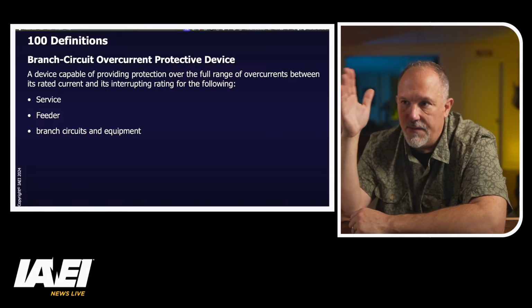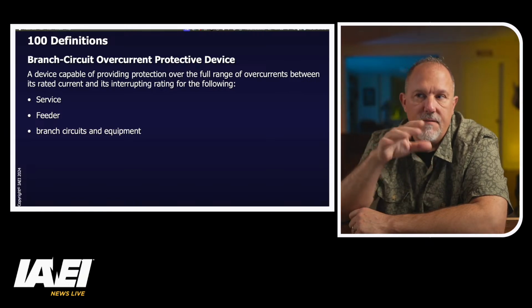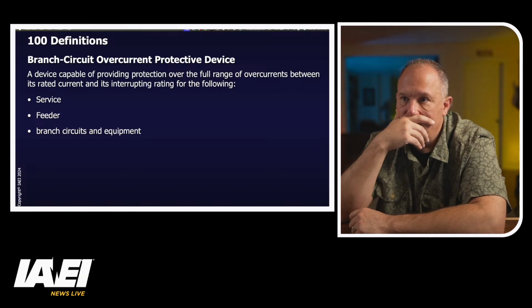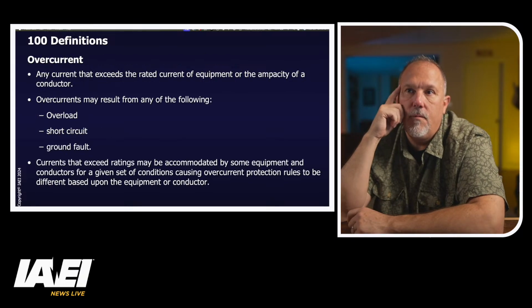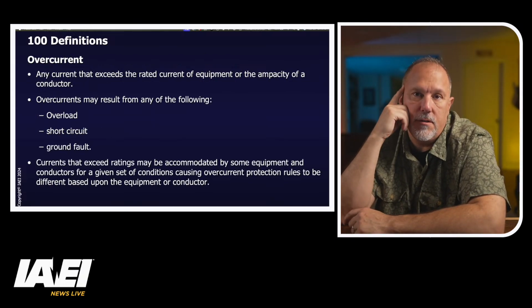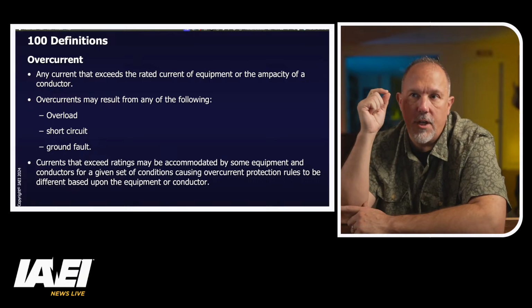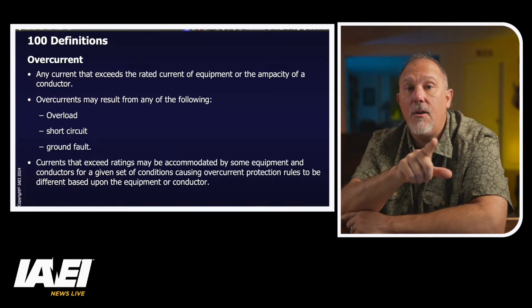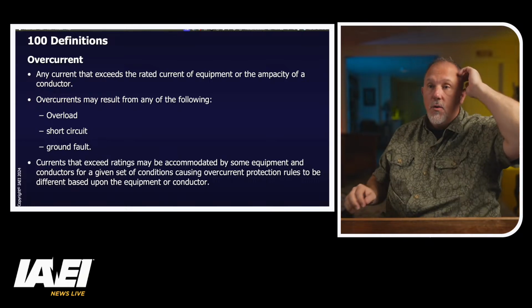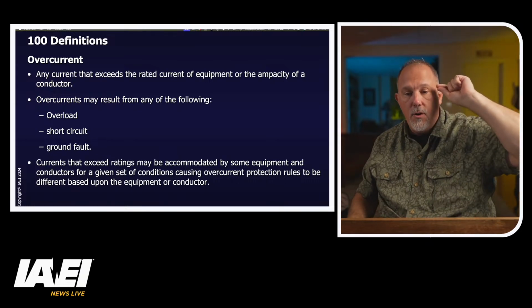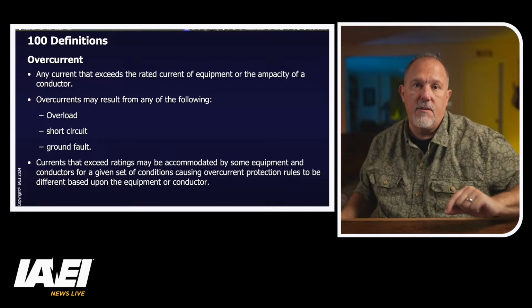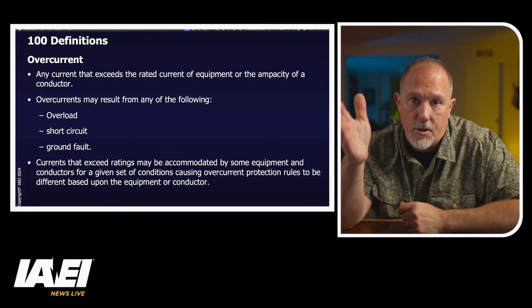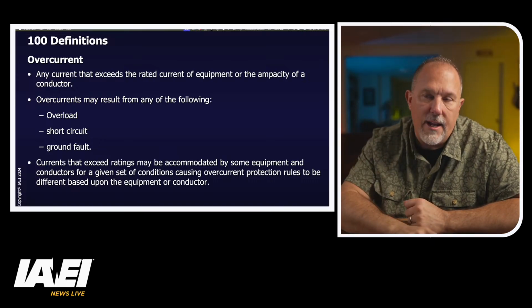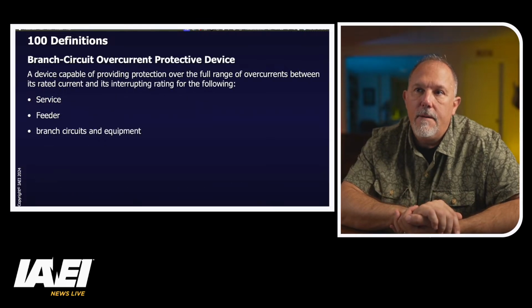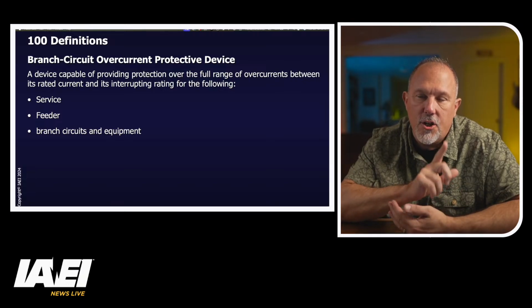So it's a very generic term. So be mindful of that. So now, overcurrents are your overloads and your short circuits and your ground faults. Now, you may say, hold on, Tom. We said that a branch circuit overcurrent protective device has to protect from all overcurrents. But remember what it said. Over the full range of overcurrents between its rated current.